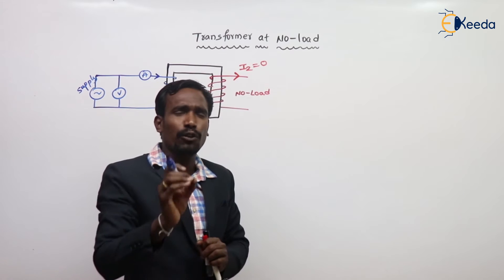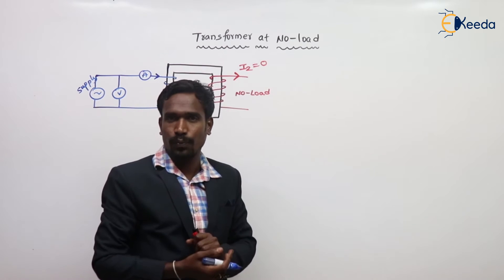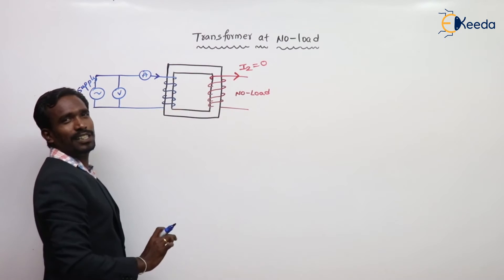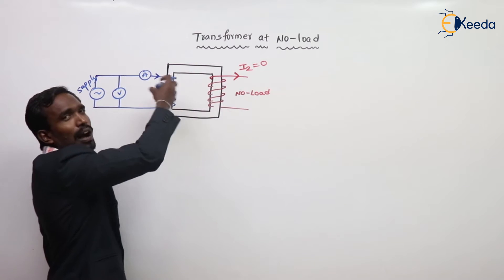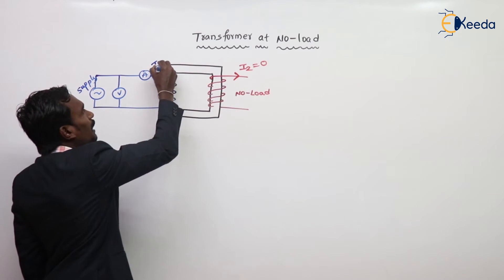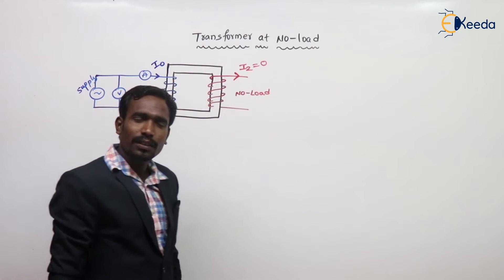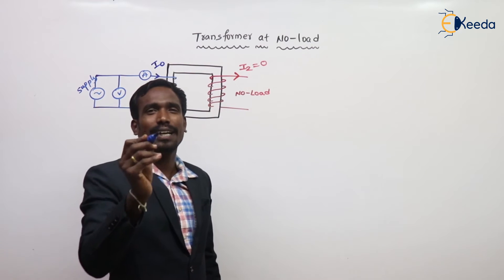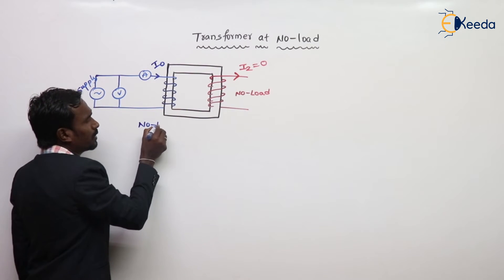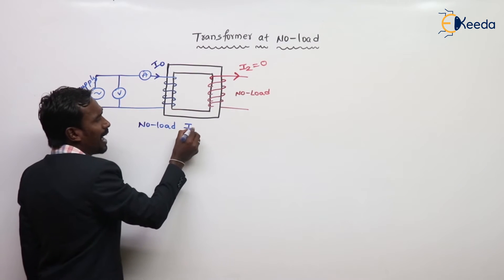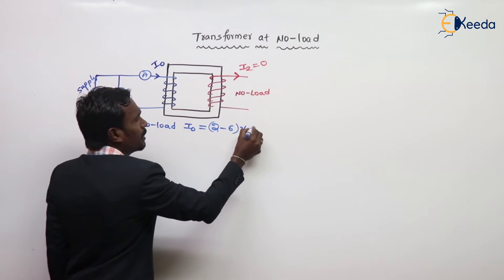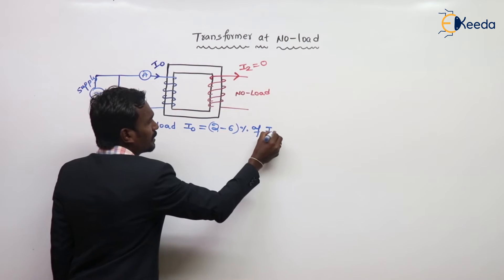In any device, if load is not connected, then current should not flow. But even under no load condition, the transformer draws a small current from the supply. That small current is called no load current I0. The no load current of the transformer I0 is equal to 2 to 6% of full load current.